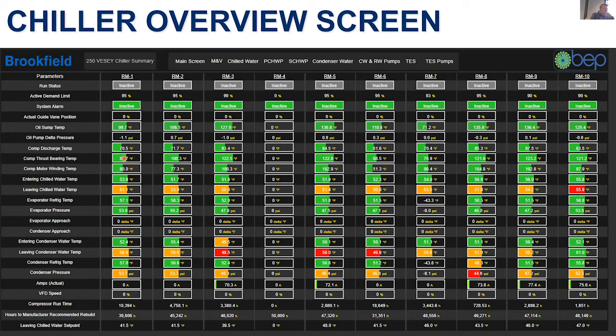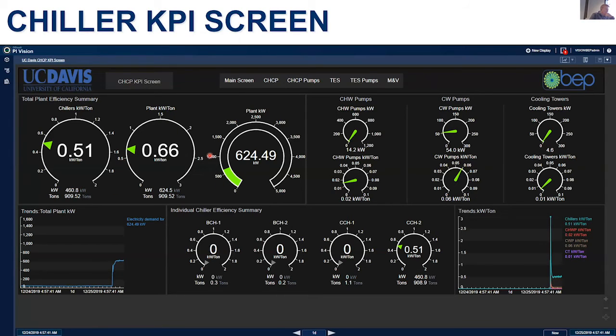So I'm going to jump into UC Davis here. You have the obligatory KPI screens. The takeaway for the audience here is, when you have these things turn yellow or orange, try not to have a static value. Try to have it be a dynamic value, because 0.66 in the summer is good, 0.66 in the winter is not good. So if I'm looking for all green, let's make sure those scales are dynamic and make sure I go granular. I don't just want total plant, break it up into components. So if the total's bad, I can quickly see on the component level which one's driving. It's a lot quicker diagnostics.